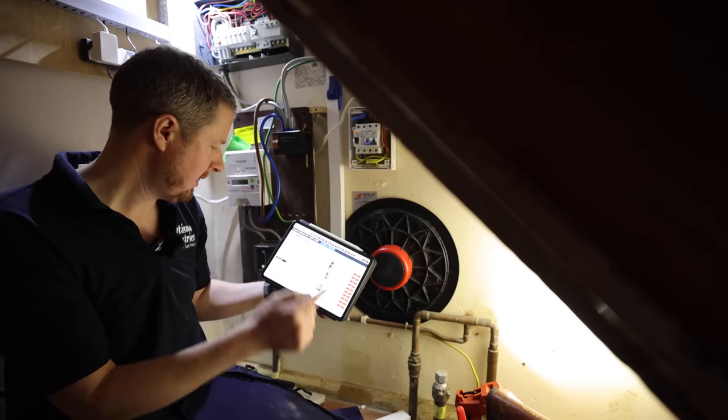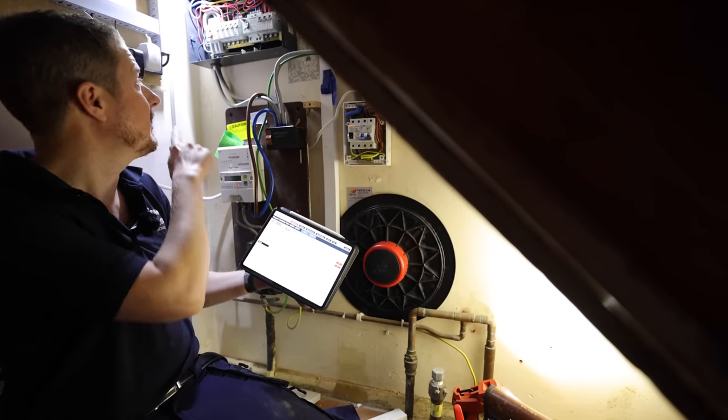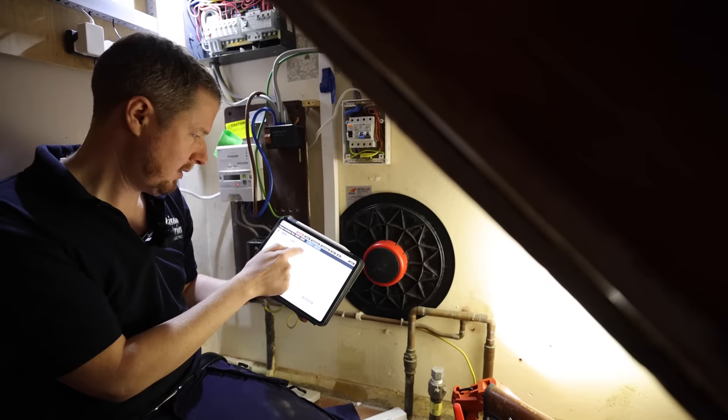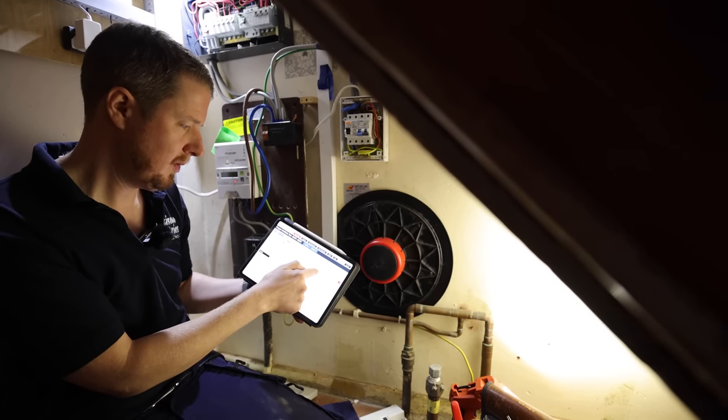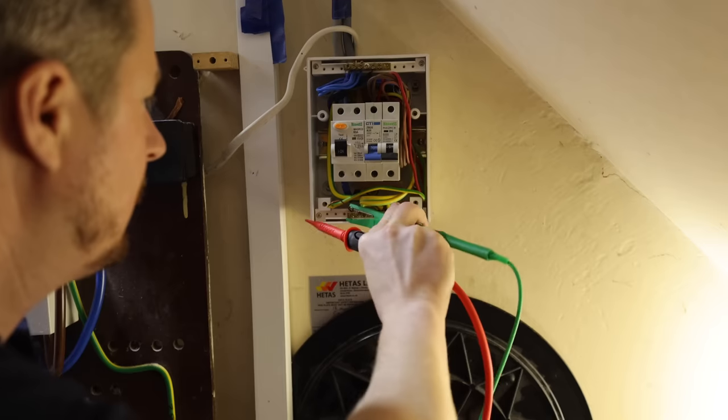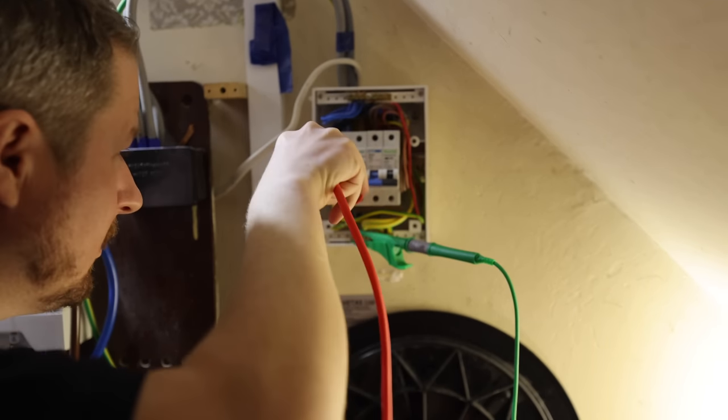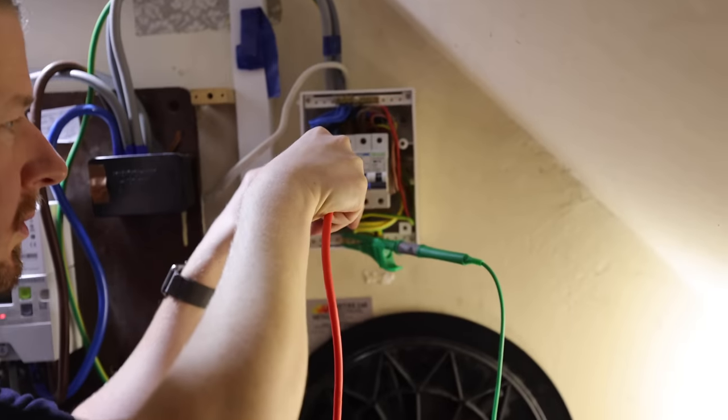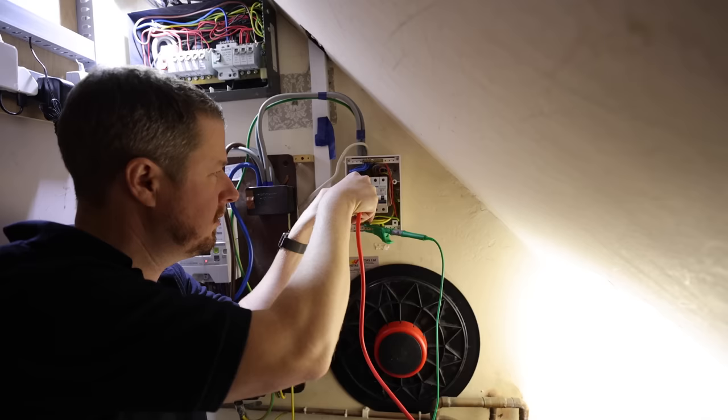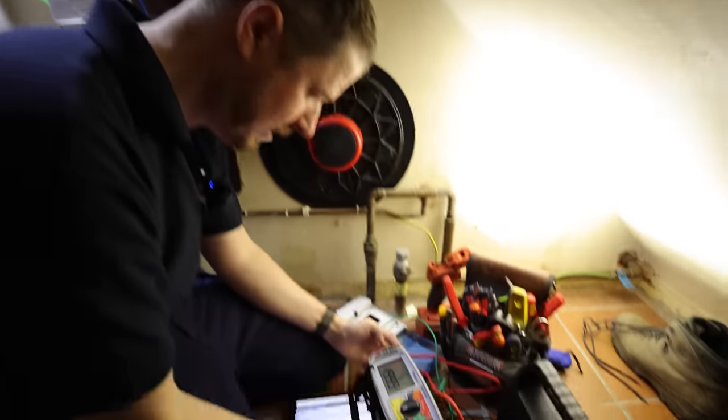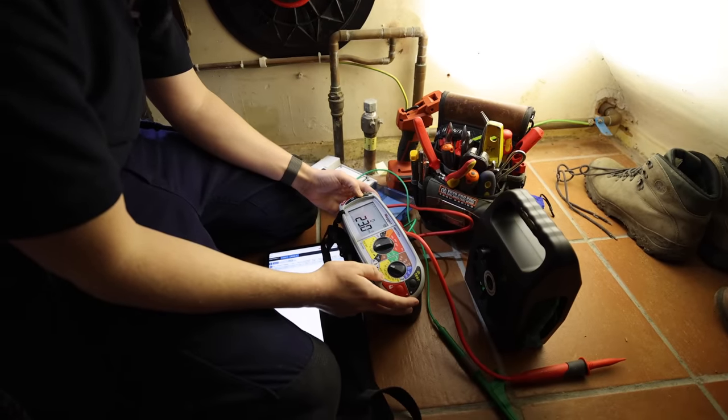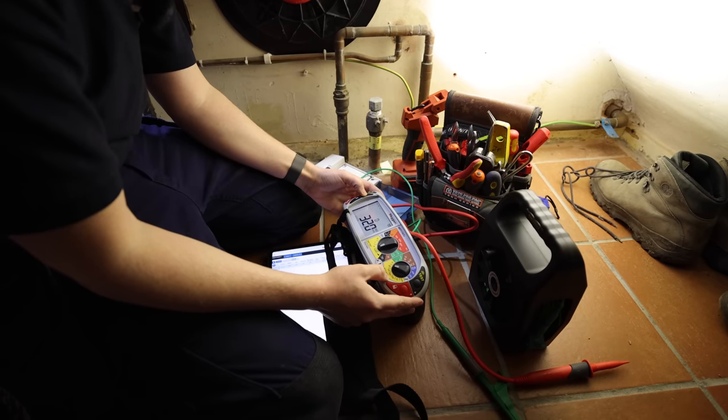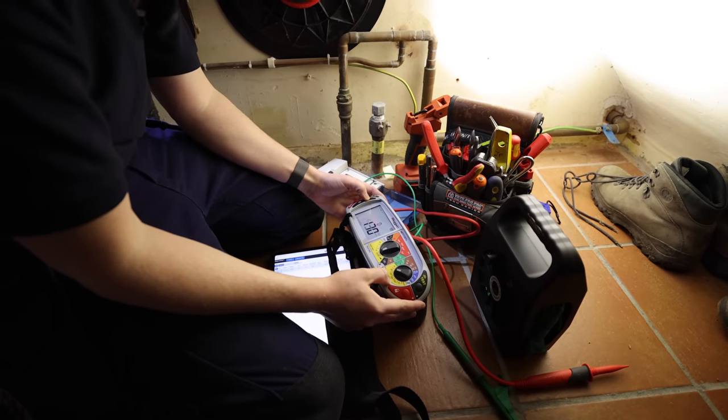So I'll show you what the full report looks like later. It looks really amazing when it's done as a PDF. So now what I'm going to do is go back to the boards and I'm going to do the RCD test readings on these two RCDs. So to do that we click on RCDs, and we just need our no trip, one times, and five times test on the main RCD first. So that is our auto RCD test done, super quick and easy, and then we can flick through the readings.